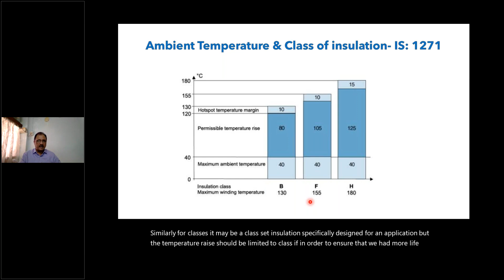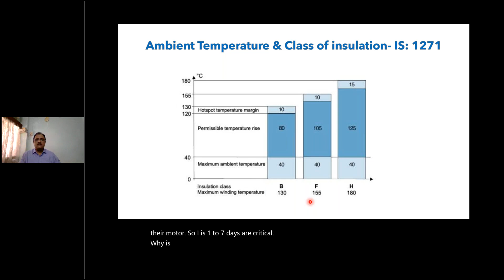So therefore, class F insulation with temperature rise limited to class B gives you a lot of advantage in terms of the life of the insulation of the motor. Similarly, for class H, it may be a class H insulation specifically designed for an application, but the temperature rise should be limited to class F in order to ensure that we get more life for the motor. So IS 1271 is a critical IS standard when it comes to the insulation class of the motor.